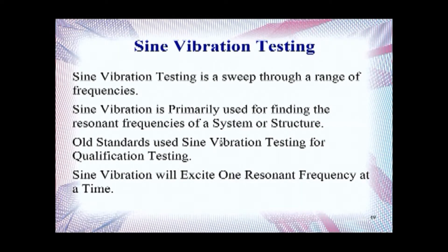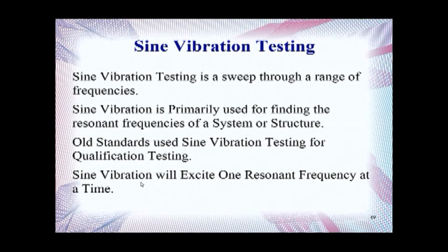Sine Vibration Testing is primarily used for finding the resonant frequencies of a system or structure. It is typically not used for actual screening or qualification testing of your unit, but in older standards, qualification testing was done using Sine Vibration Testing due to the limitation of technology at the time — random vibration was not feasible at one point in time. Sine Vibration will excite one resonant frequency at a time, which is why it is not useful for finding all the failure modes for your test. That's why you need more complex vibrations or random vibration testing.